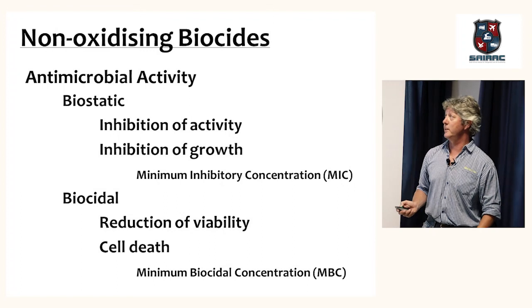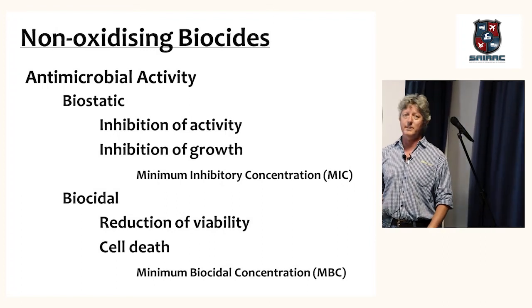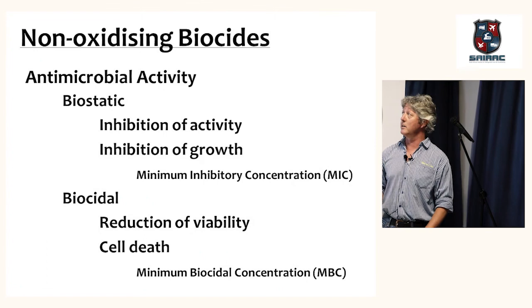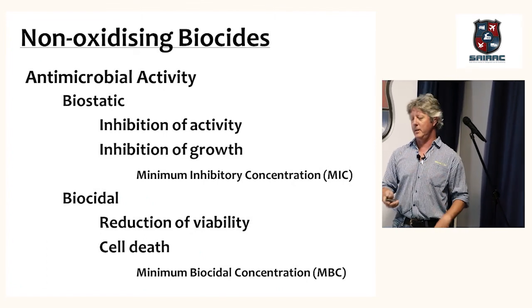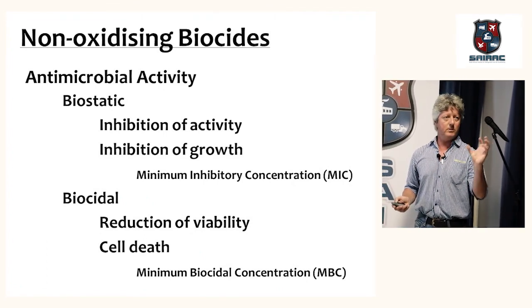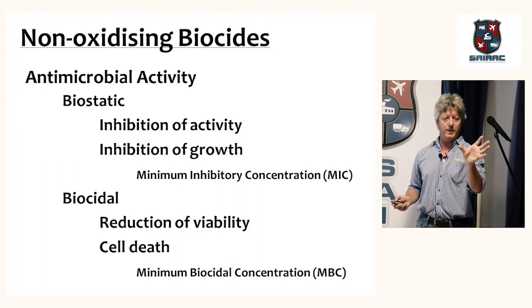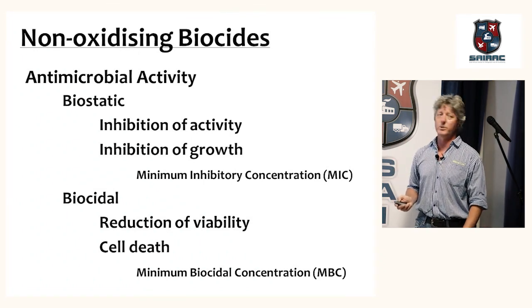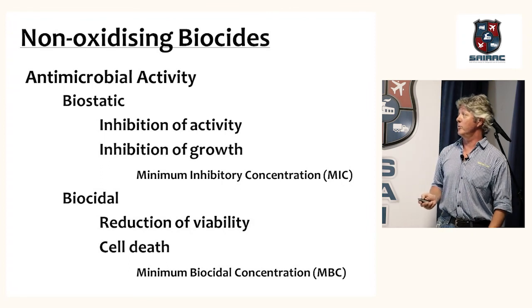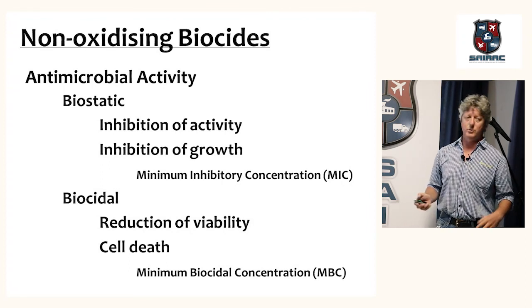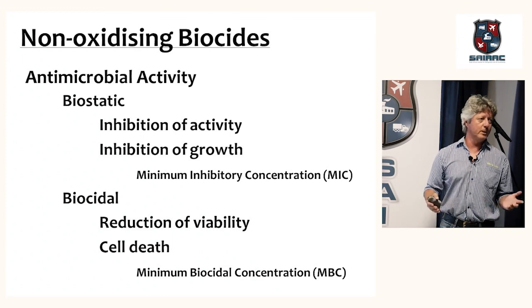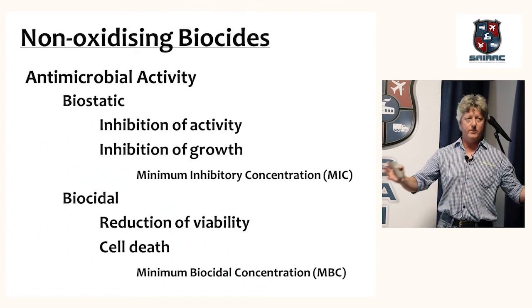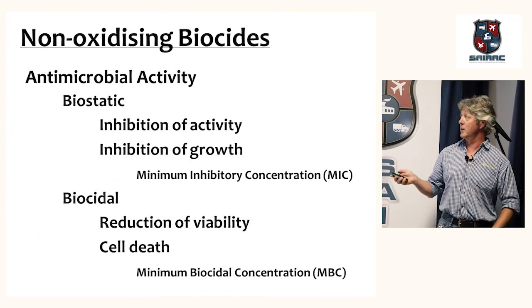Non-oxidizing, it's also got antimicrobial activity. It's biostatic, which means it's not biocidal. It basically keeps the status quo. In other words, if there's 1,000 there, there will still be 1,000 there, but they will not be able to proliferate. Inhibition of activity, inhibition of growth, and then you have your minimum inhibitory concentration, which is normally calculated in parts per million. So you dose X parts per million of product, and you know you've basically covered this MIC.